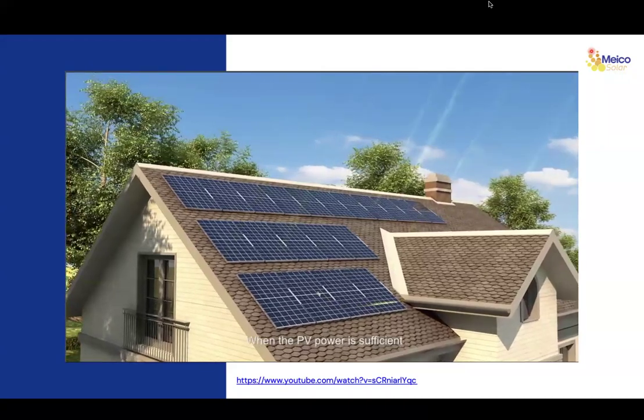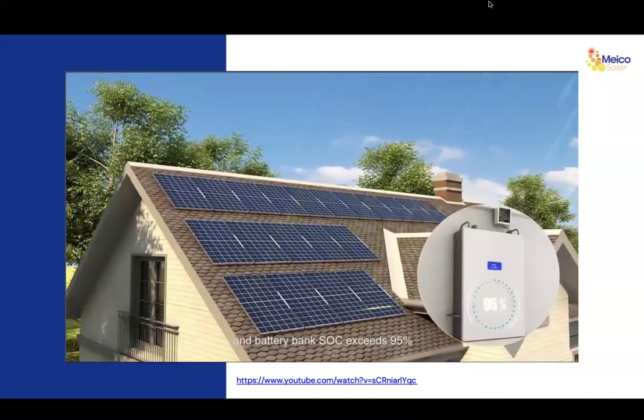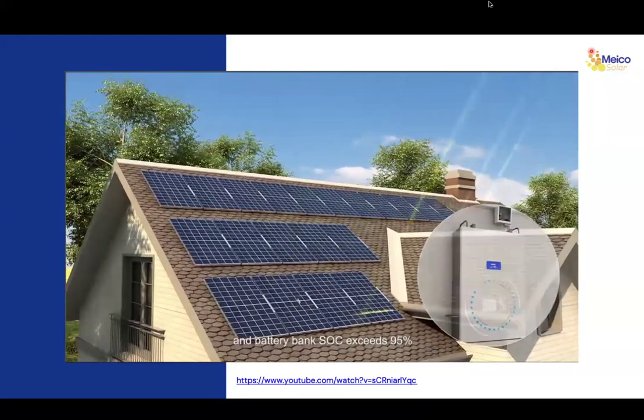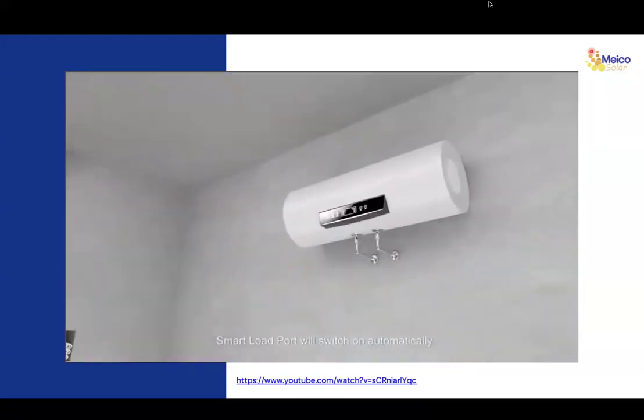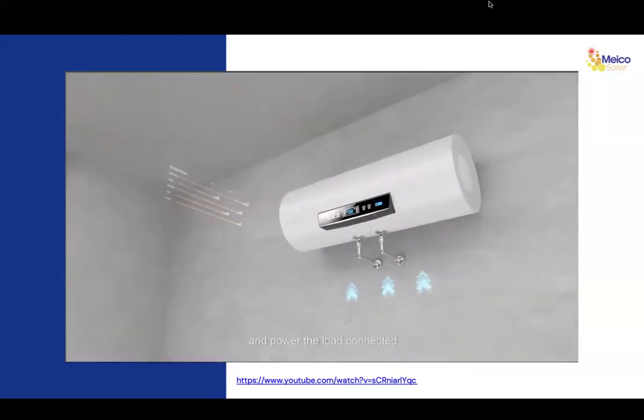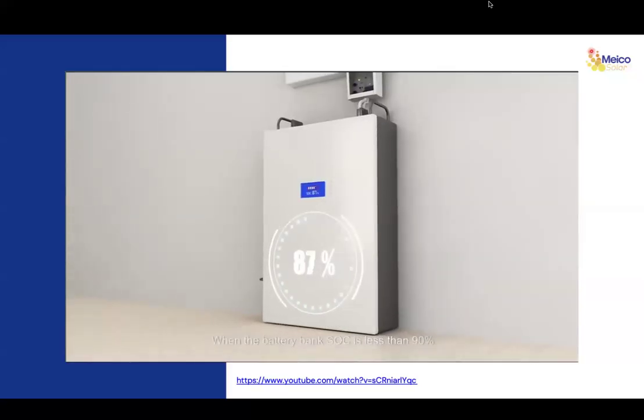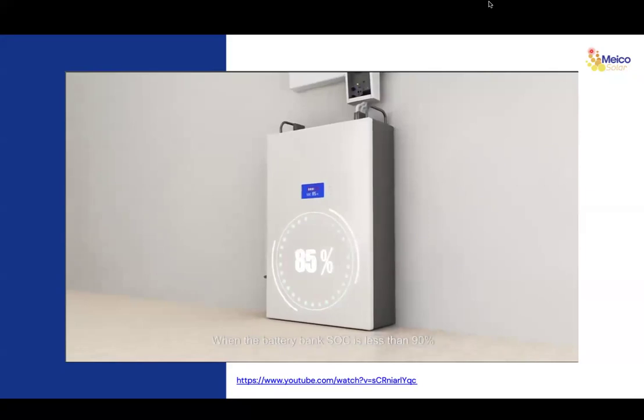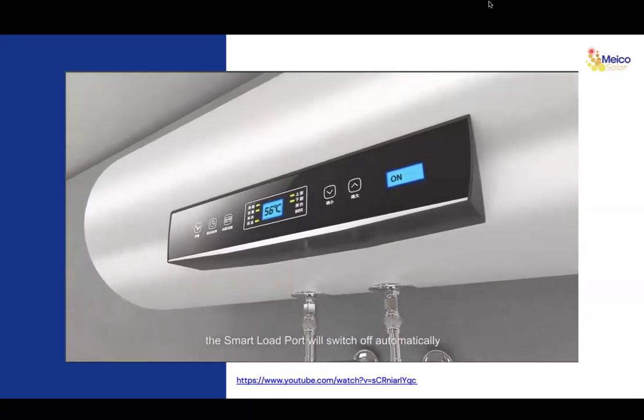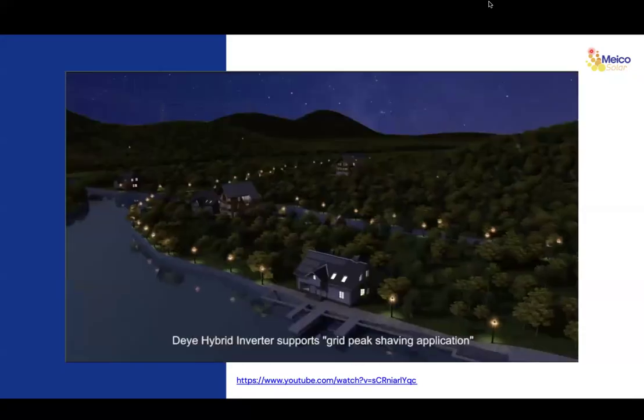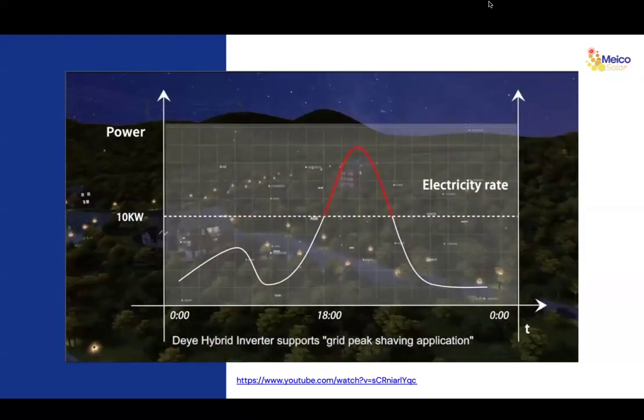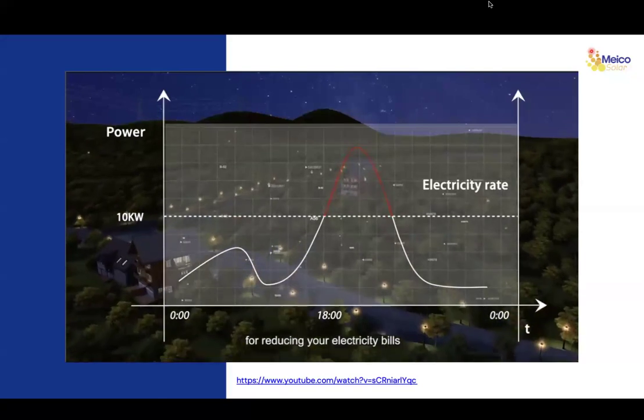When the PV power is sufficient and battery bank SOC exceeds 95%, the Smart Load Port will switch on automatically and power the load connected. When the battery bank SOC is less than 90%, the Smart Load Port will switch off automatically. Deye Hybrid Inverter supports grid peak shaving application for reducing your electricity bills.